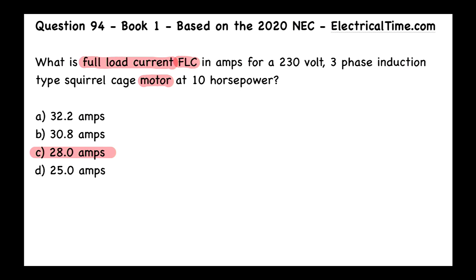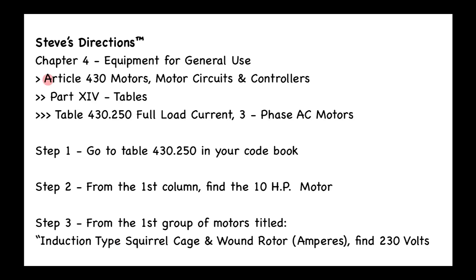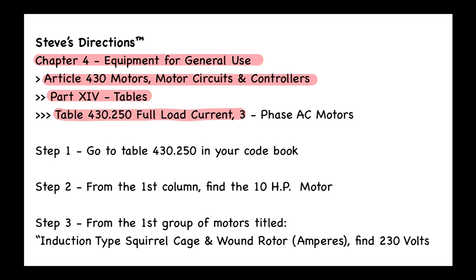Article 430 is called 'Motors, Motor Circuits, and Controllers,' and that's within Chapter 4, Equipment for General Use. We go all the way to the end of Article 430 and find Part 14, called 'The Tables.' We then look at Table 430.250, which covers the full load current for three-phase alternating current AC motors. Step one: go to Table 430.250 in your code book.